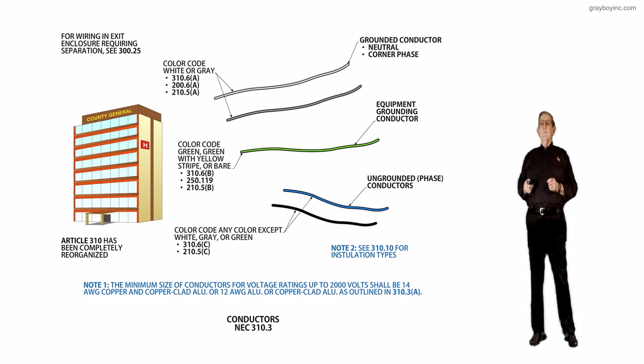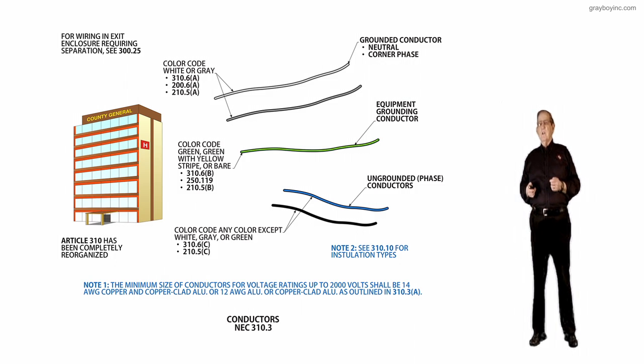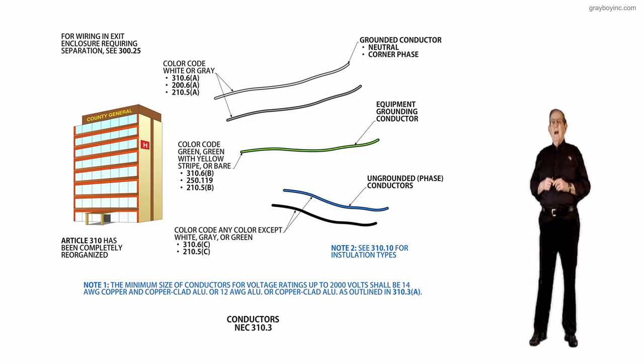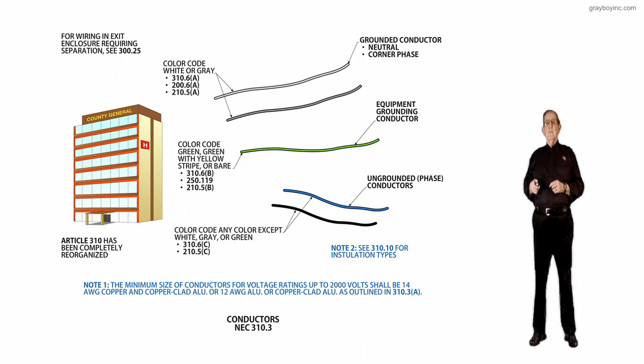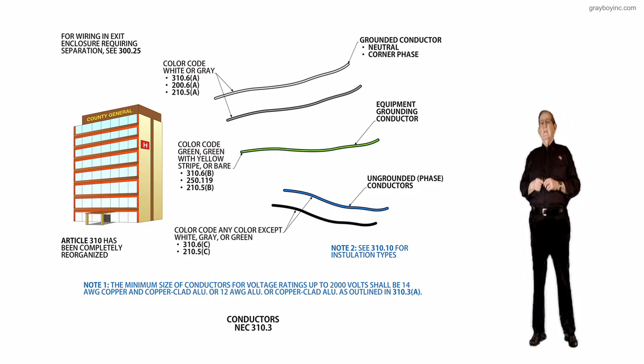First I would like to review the ungrounded phase conductors. What color could they be? Well they could be any color except white, gray or green as required in 310.6C and 210.5C, depending if you're a feeder or a branch circuit.